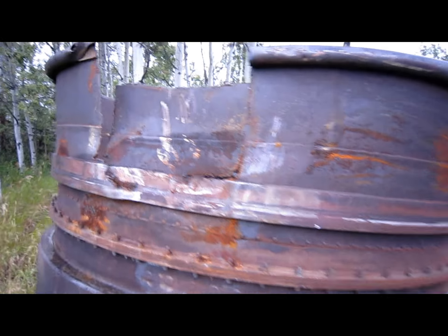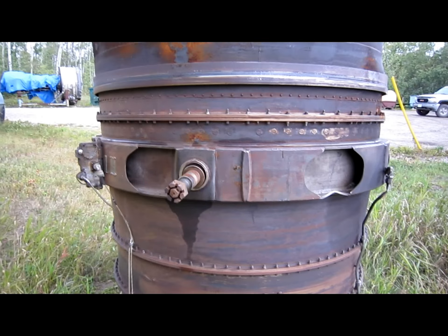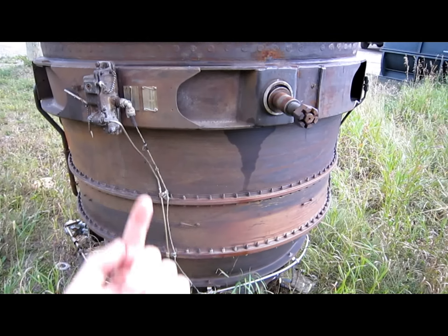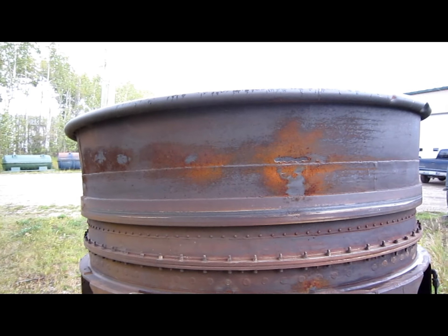There's the back end of the power turbine, and it is turned by the gas that's coming out of the turbine engine, or jet engine. These are the struts. Those struts support the main bearing which is right down in there. This big ugly thing is a power turbine. You can see that a power turbine looks a lot like the back end of a jet engine because it's built exactly the same way — just larger, for slightly lower temperature and lower velocity. Instead of the shaft going to the front, the exhaust gases come this way into it, so instead of the turbine shaft going forward to drive a compressor, the shaft goes out the back and drives the mechanical load, whatever that might be.